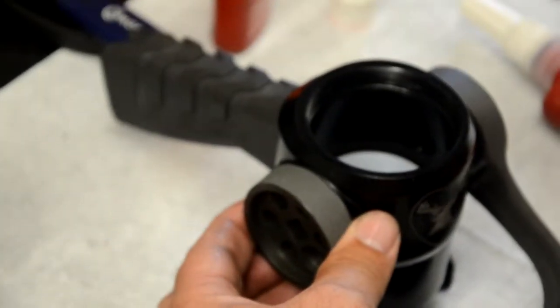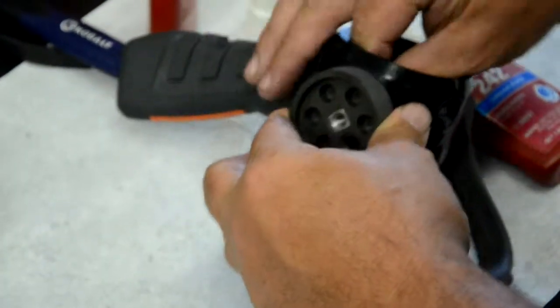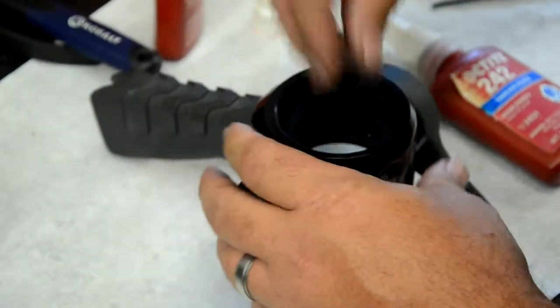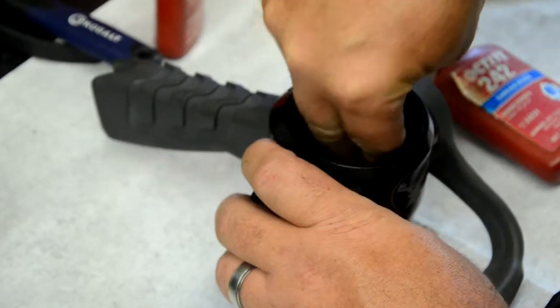Next, install the actuator shafts by pushing them through the inside of the nozzle body. Make sure the flats of the actuator shaft run parallel to the waterway. If they're not, we won't be able to install the ball valve in the next step.